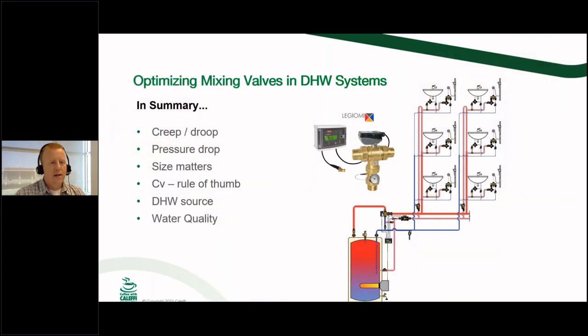All right, now let's quickly summarize. We talked about creep, we talked about droop, we talked about pressure drop, we talked about sizing of mixing valves. Again, oversizing a mixing valve can be just as detrimental as undersizing a mixing valve. We talked about CV and how you can use that to compare mixing valves, or any type of valve, whether it be a zone valve or a balancing valve or whatever. You can use that as a good benchmark. And we talked about your domestic hot water source as well as your water quality.